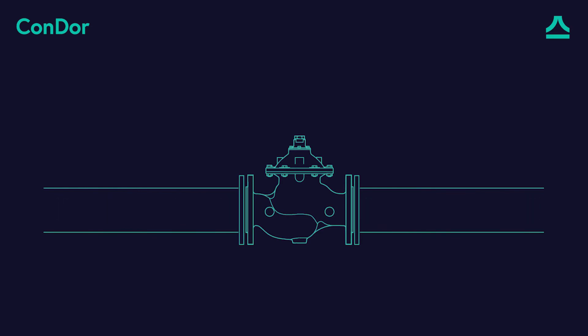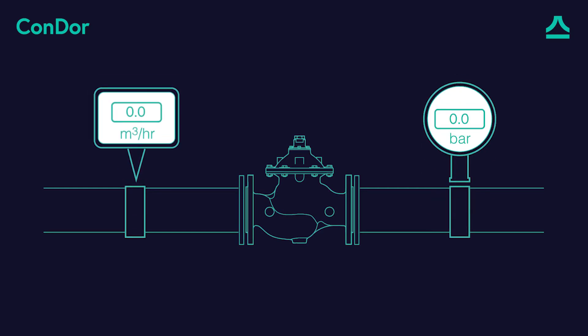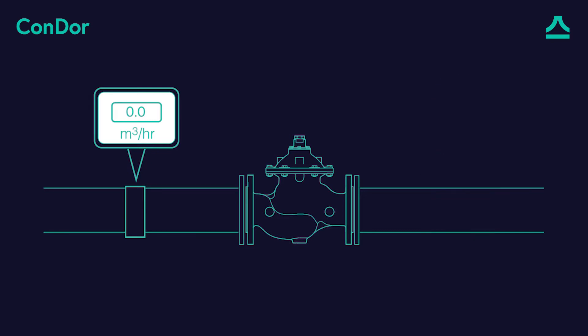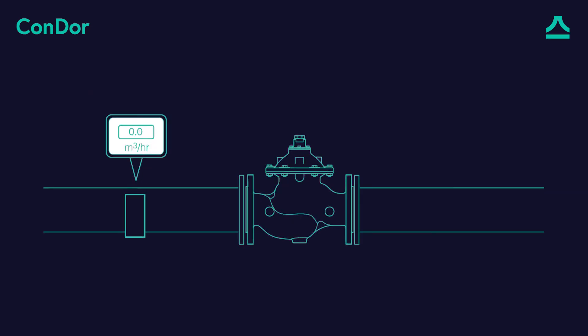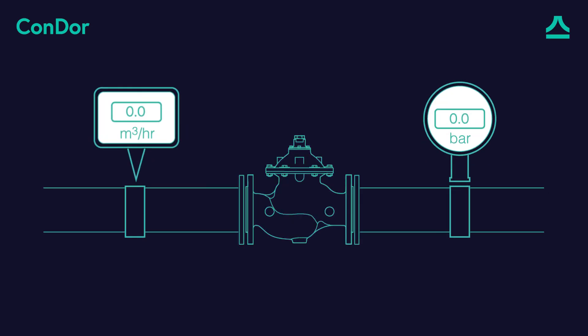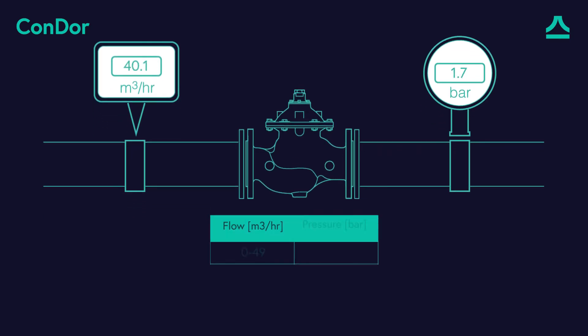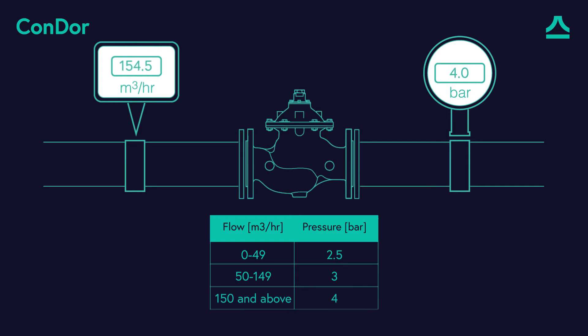First, write down a table of the relation between flow and pressure according to the customer's needs. In this example, we want to keep a fixed pressure for the range of the flow. We will define the steps in a table according to the following parameters: for a flow up to 50 cubic meters per hour, the required downstream pressure is 2.5 bar. For a flow between 50 to 150 cubic meters per hour, the required downstream pressure is 3 bar. For a flow above 150 cubic meters per hour, the required downstream pressure is 4 bar.